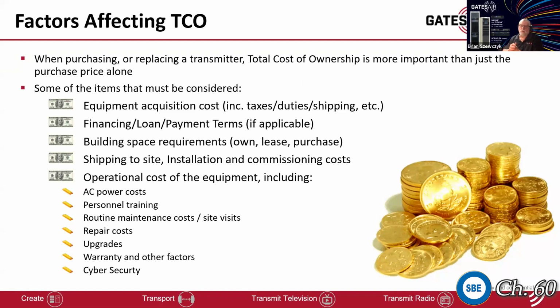And another thing that's really creeping in is cybersecurity. When you have a transmitter plant that is monitored, modern transmitter plants and facilities have a lot of SNMP monitoring going on. You want to make sure that what you're installing in there isn't opening you up to a cyber attack, which can be very costly.